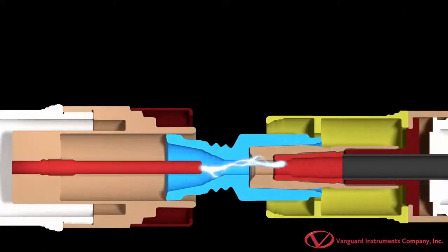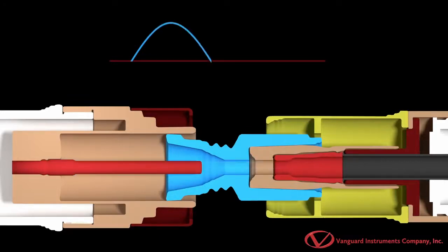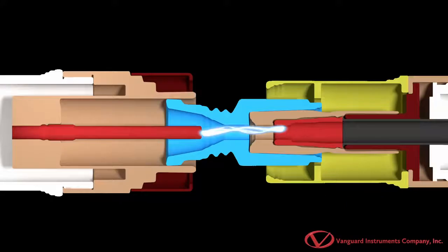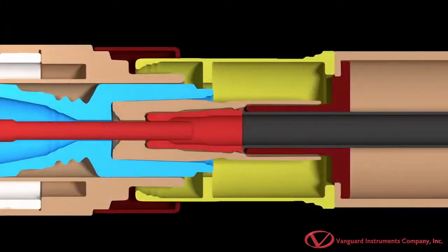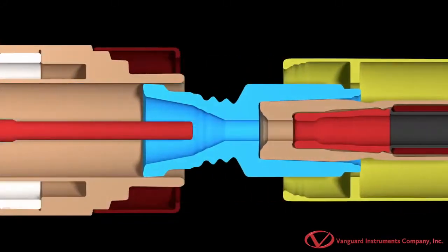When the contacts open, an arc is created due to current interruption. An AC arc extinguishes at every zero current level, but reignites immediately after crossing the 0 point due to the presence of voltage across the open contact. In order to avoid arc reignition, the contacts must be separated with sufficient speed, and the dielectric strength across the open contacts must be able to withstand the transient voltage.